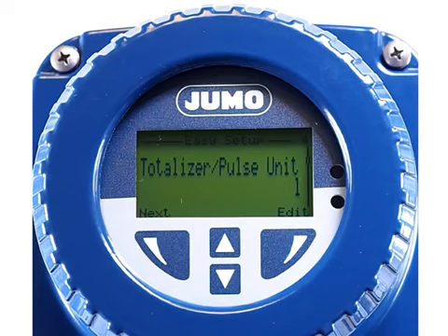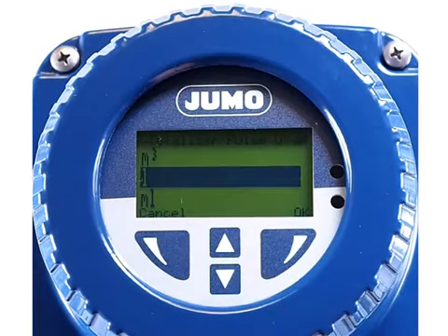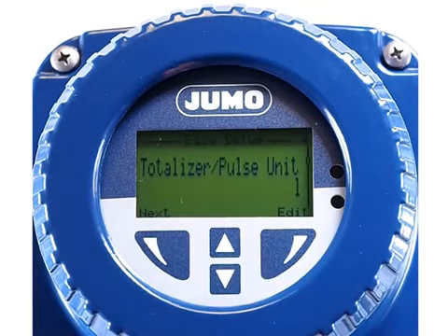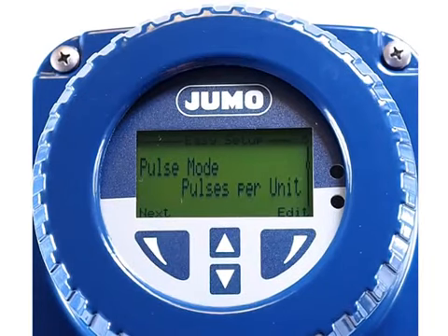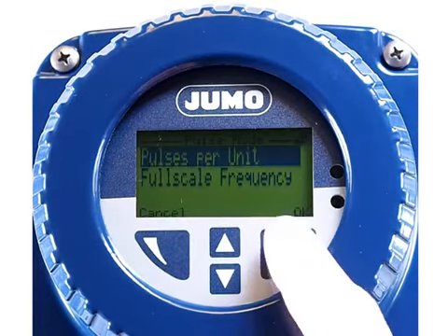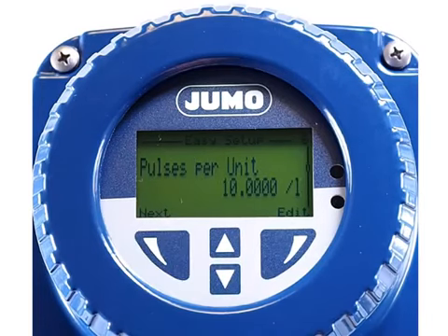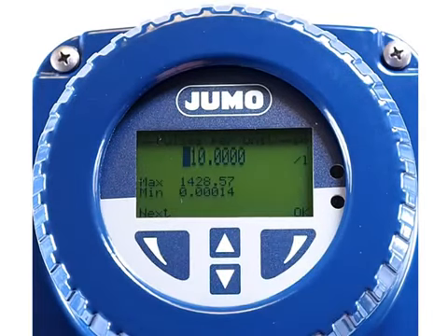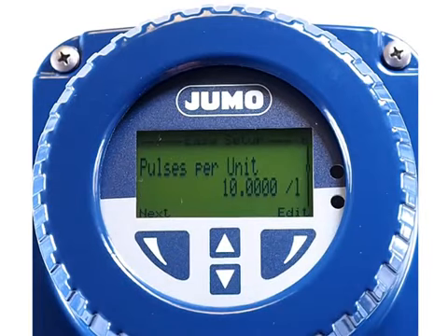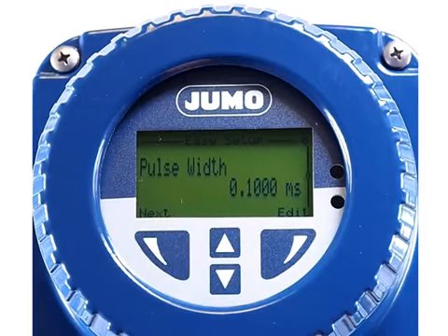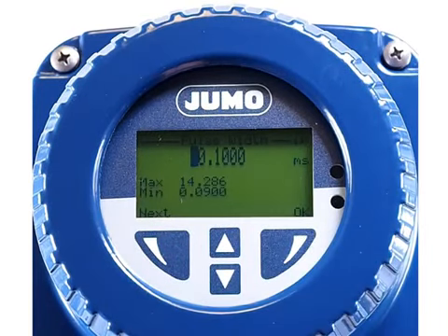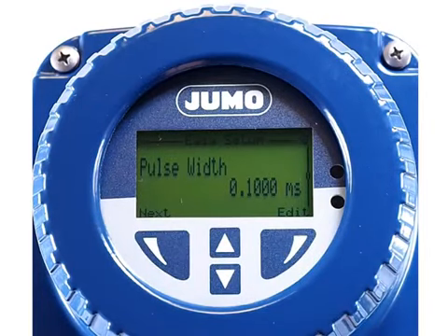Besides the current output, the device also features a pulse output, as it is used for example in simple paddle wheel sensors. The unit for this output is adjusted along with the unit of the totalizer at this point. If the pulse output is to be used, we can now configure the number of pulses per unit. Again, this value is also used in the field device to interpret signals correctly. If the field device requires a minimum pulse width, this can be set here.